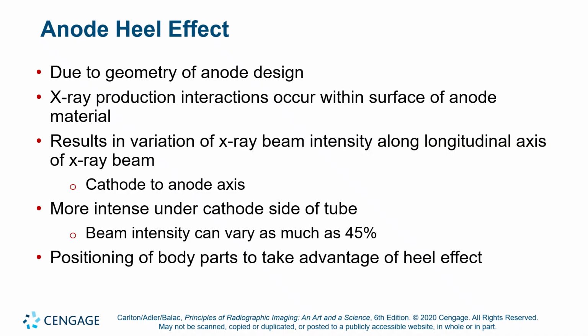Okay, anode heel effect. We have this rotating anode, and we have to have a heat sink in the base. So there's got to be a large mass in back of the target surface, and that has to extend down beyond the target surface, in the direction of the patient. Because of that, there's matter there. Now we're sending an X-ray beam in all directions, but part of the beam that actually becomes the useful beam travels back through the heel.